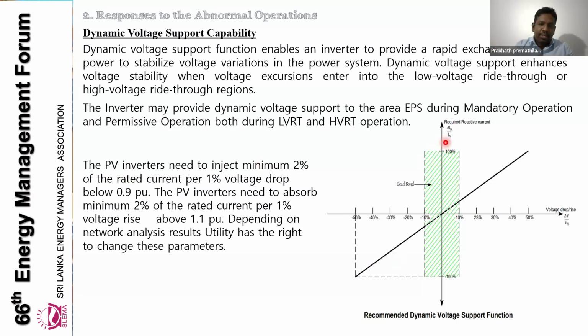But there is a dead band. Of course, we know that from 0.9 to 1.1 is a dead band, where we don't need any kind of support. Beyond this point, if the voltage drops by 1%, they can inject a minimum of 2% reactive current. If the voltage increases by 1%, they can consume reactive power by 1% or 2%. Likewise, we can define dynamic voltage support capabilities in the inverter itself. So in these situations, if we need some reactive power, the inverter can support.